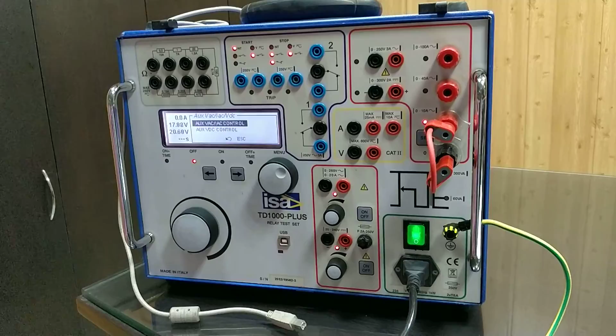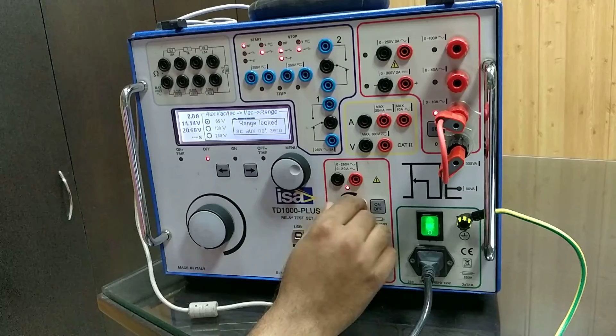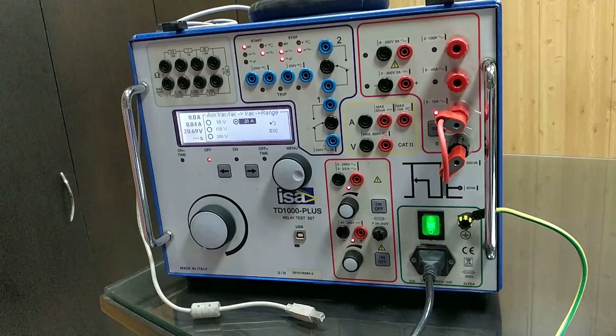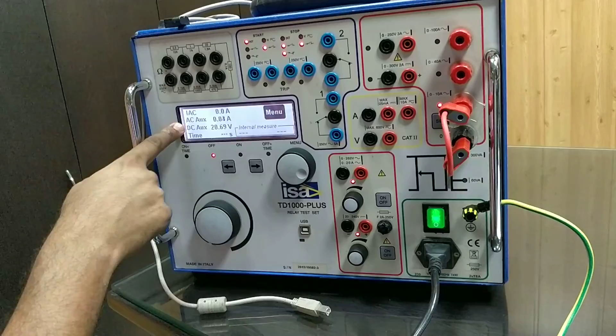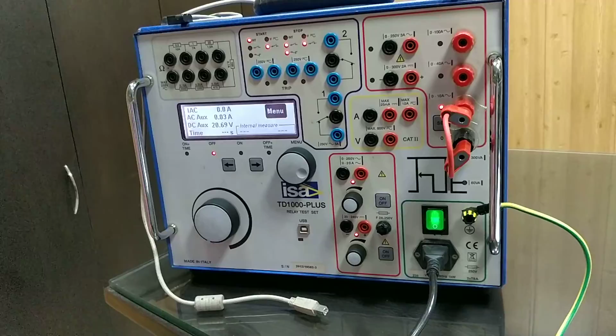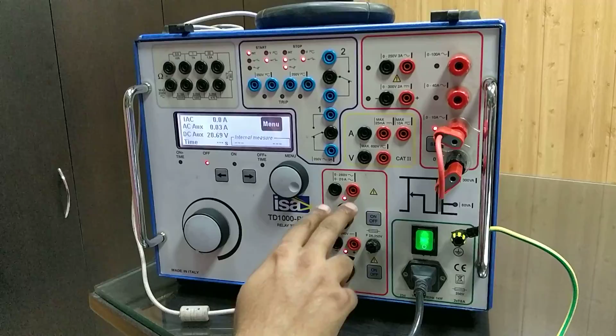To generate that auxiliary current source, we have to select auxiliary AC and auxiliary DC from the main menu. Inside the auxiliary AC, we can select range, and inside the range we have to select 20 amperes output. And now you can see on the display screen the auxiliary AC with amperes. So here we can generate the current output from the same terminal.